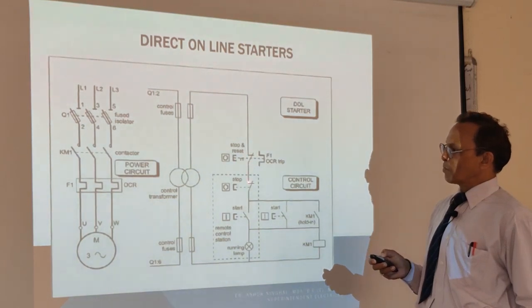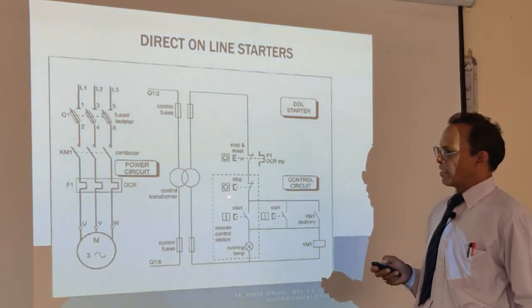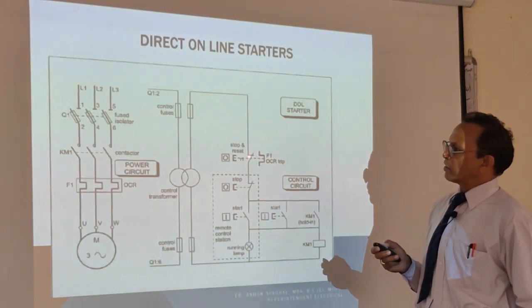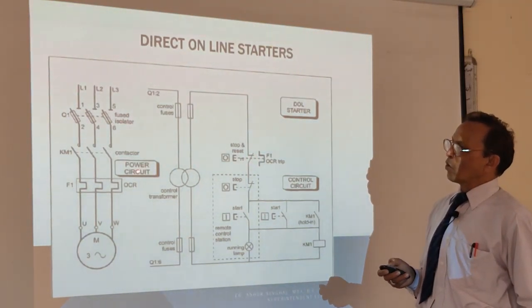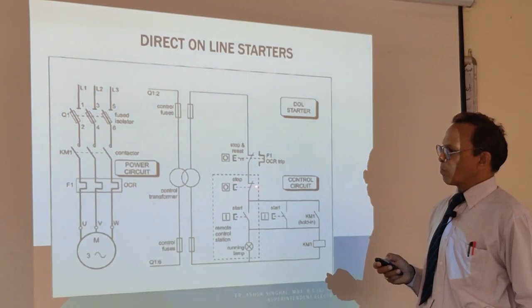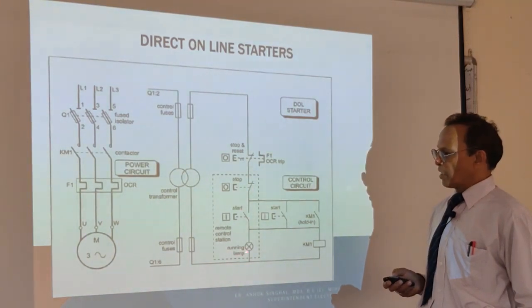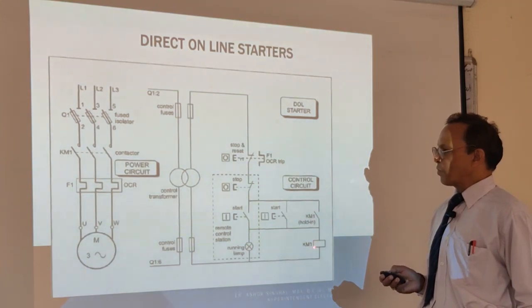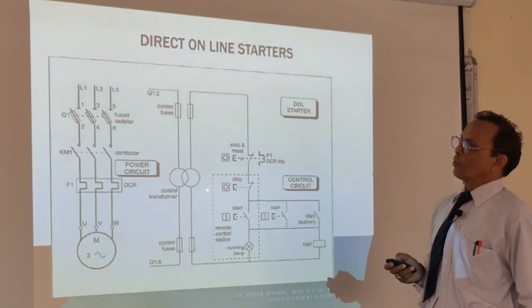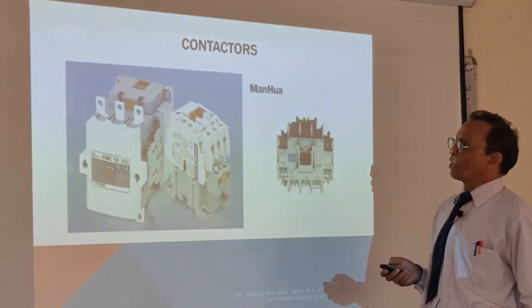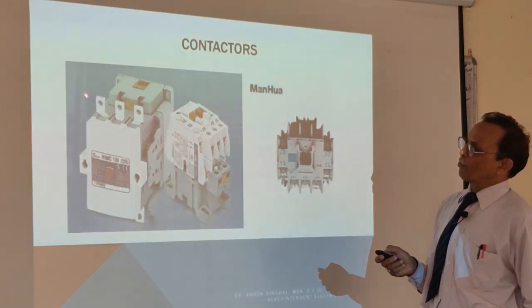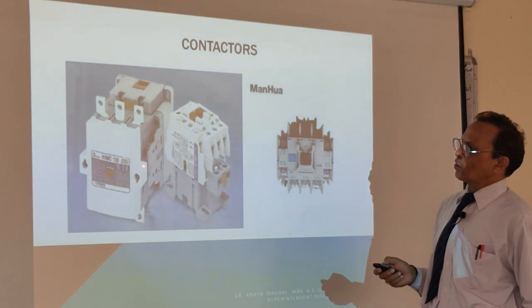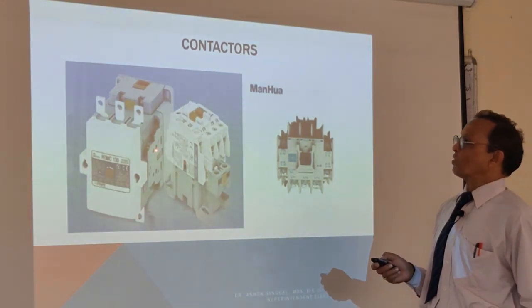From 220 volts, this is the control circuit from the secondary winding of the step-down transformer. Power is coming through and waiting at this point, and on the other side it is coming and waiting at this point. This is the contact for the overcurrent relay, the stop contact, the start contact, the running lamp, the KM1 contact, and the holding-on contact for KM1. The contactor has 440 volt main contacts and auxiliary contacts including the holding-on contact.